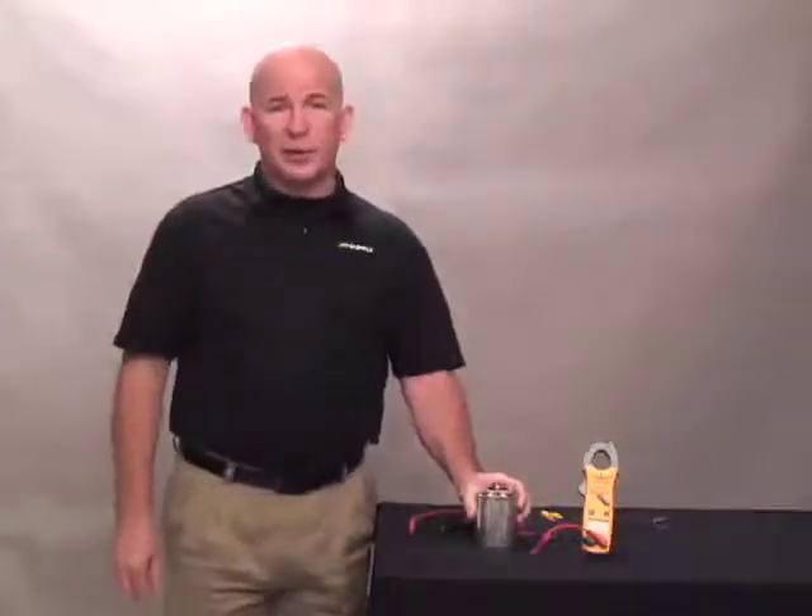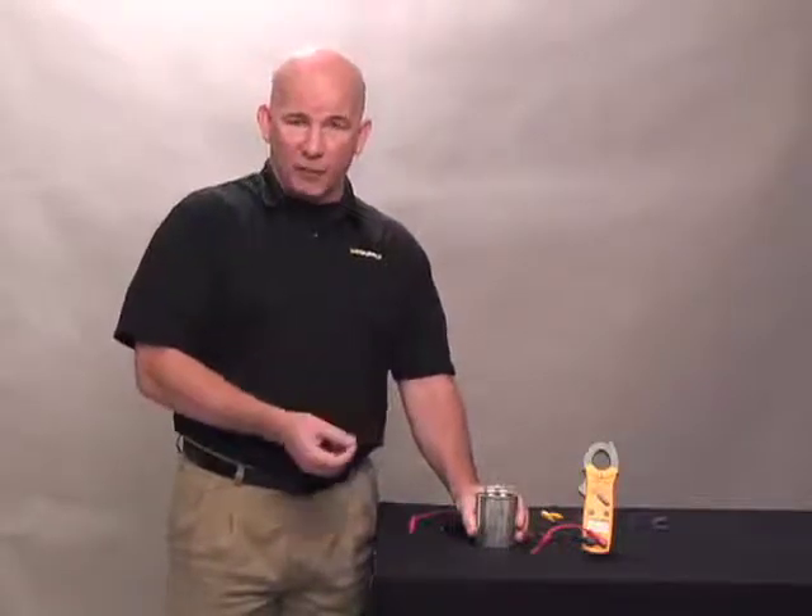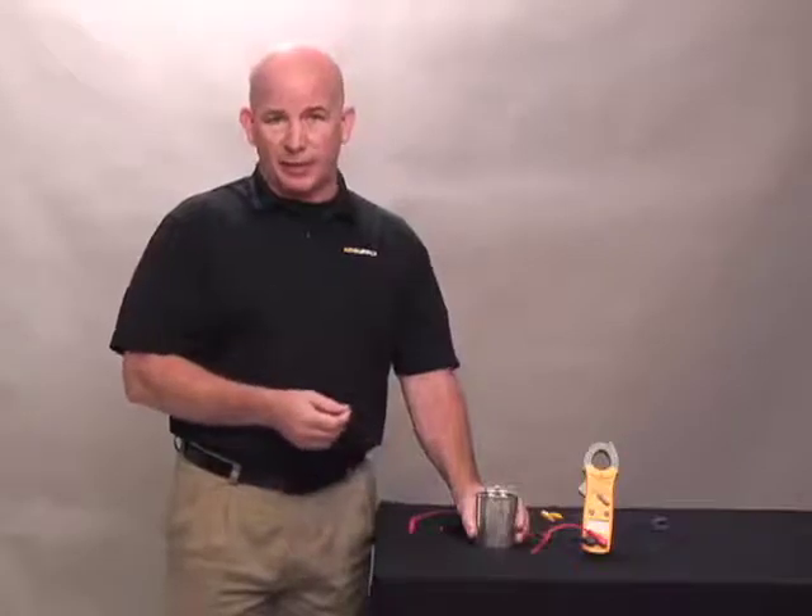This is a standard 25 plus 5, 440 volt capacitor. 25 is the microfarads for the run of the compressor, 5 is the microfarads for the run of the fan, and 440 is the maximum amount of voltage that this capacitor can handle.